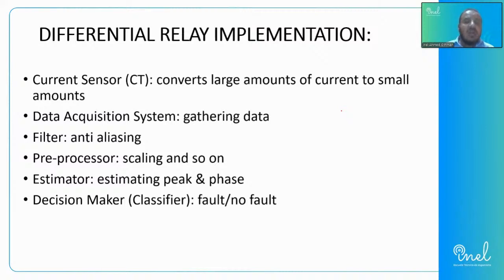We have a filter, we have a processor, we have an estimator, and at the end we have a decision maker, which classifies the data and sends a signal based on whether there is a fault or no fault. So at the end, such a relay feeds the circuit breaker to tell it there is a fault, please trip, or there is no fault, please continue. So those are the implementation map or structure of any differential relay.